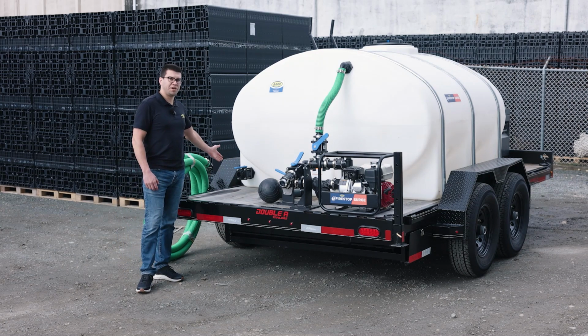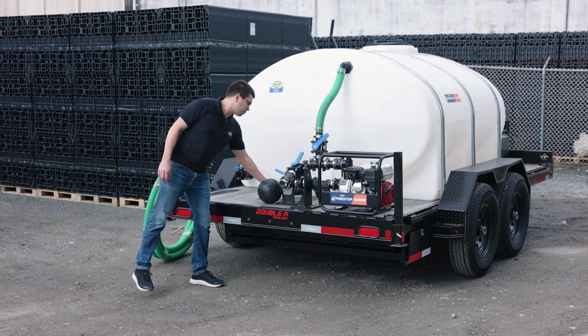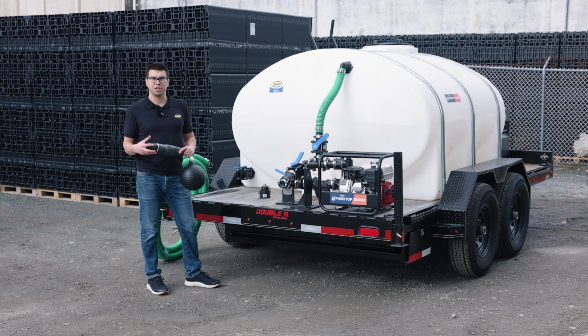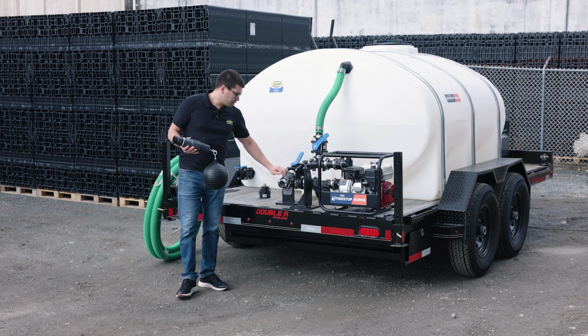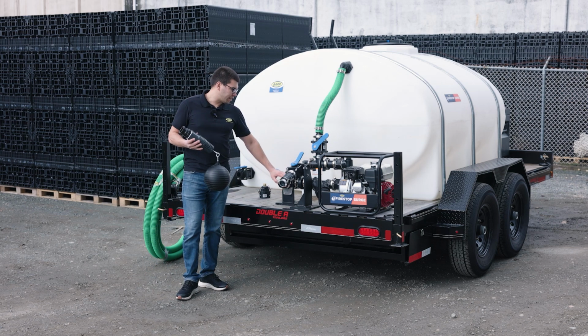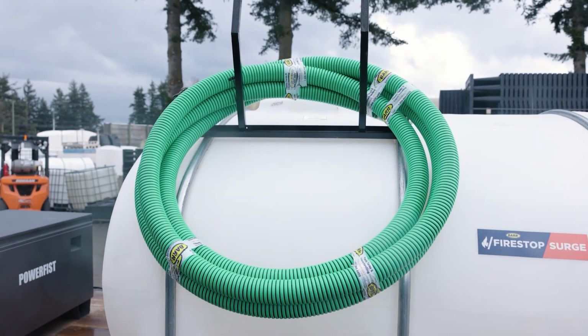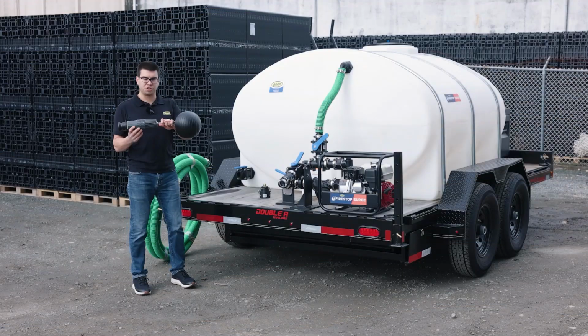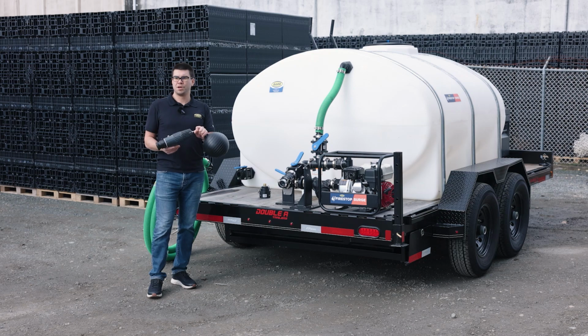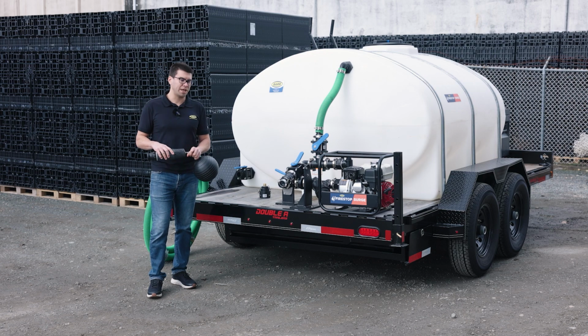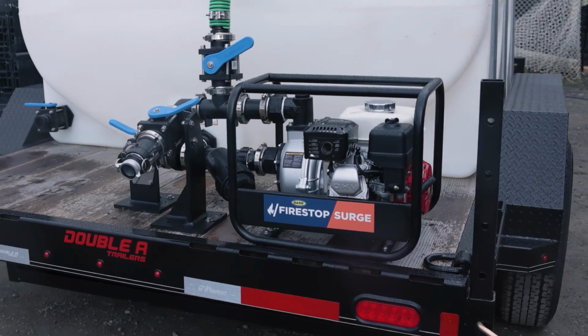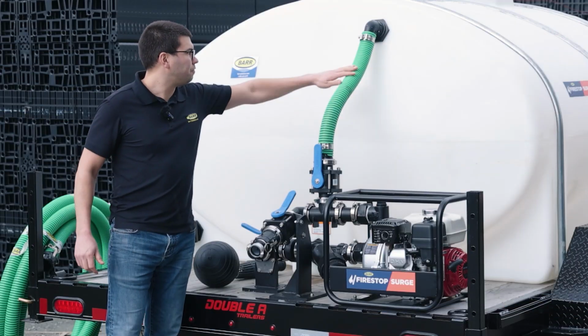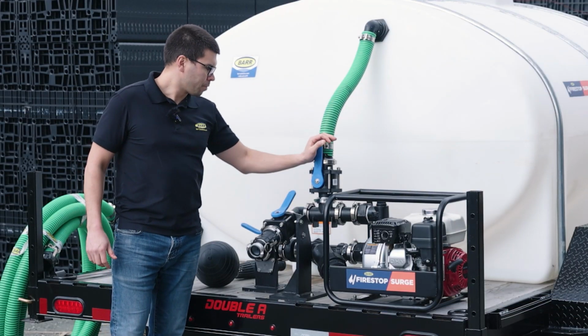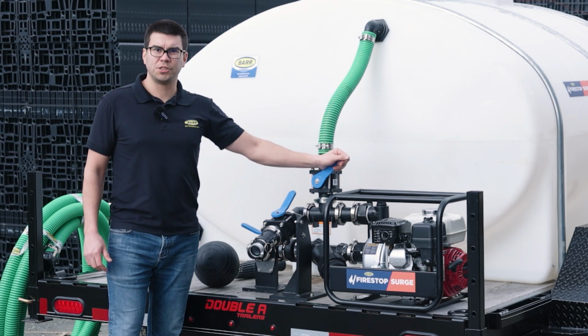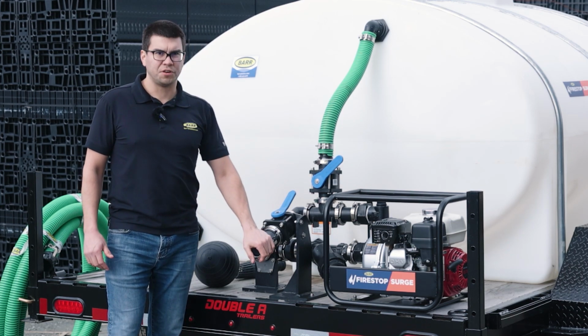So we have a 2-inch valve here that you could use an off-board pump to fill through, or we have a floating suction assembly that we have available as an optional addition to these units that you can use the onboard pump to connect a 30-foot hose to with the floating suction assembly that'll make sure you're drawing clean water out of a water source, a lake or stream or anything external like that. So you'll use the pump suction, use the onboard pump, and then you can fill the tank through this line here. Once the tank is full, you can switch it to the fire hose for discharge.